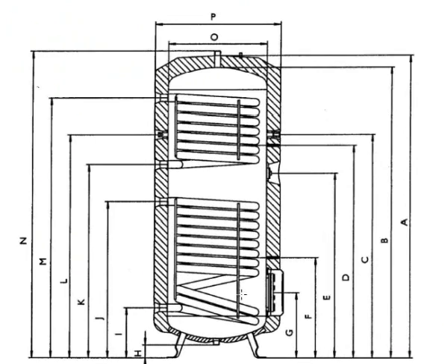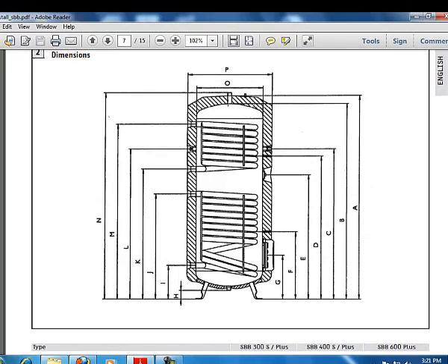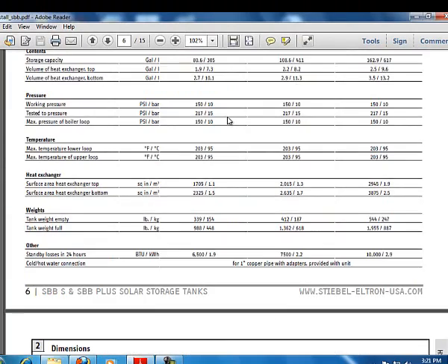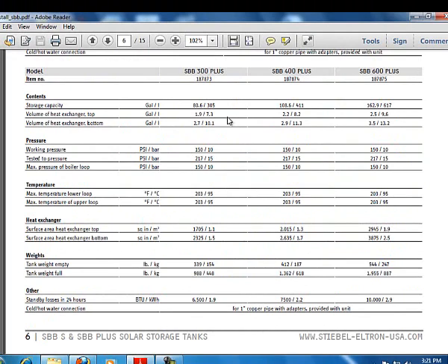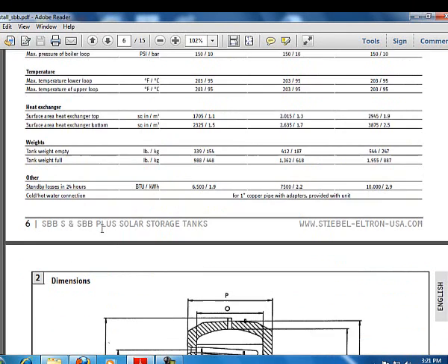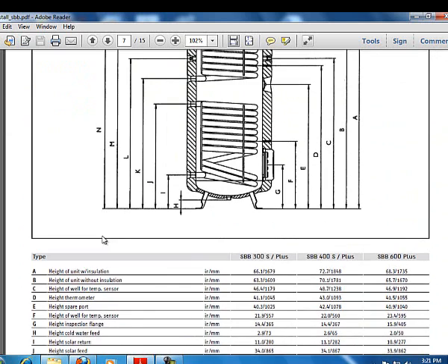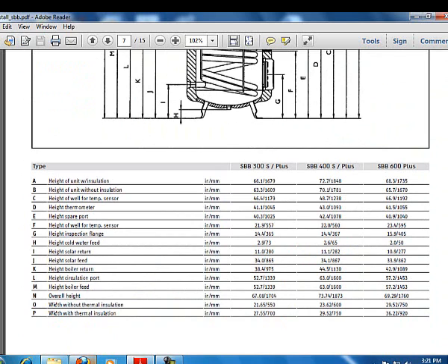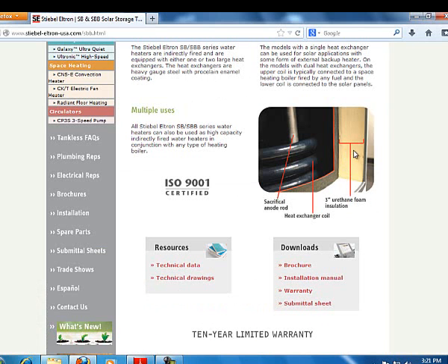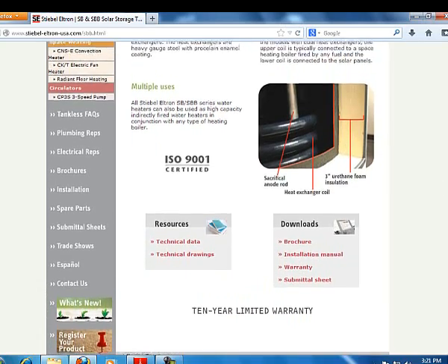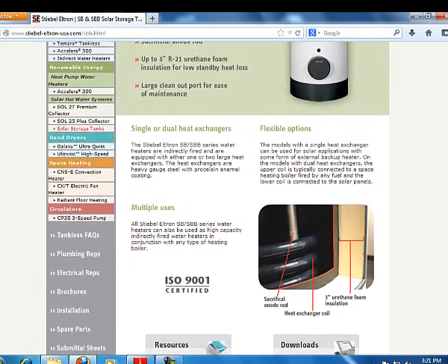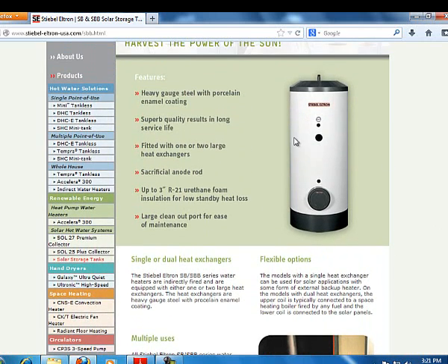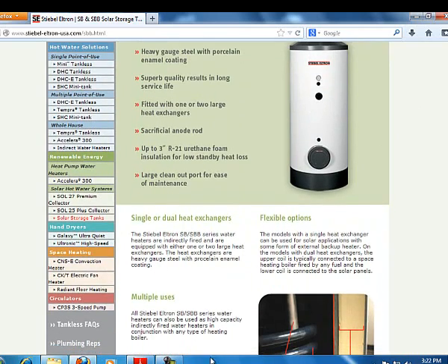You can kind of see how this tank takes the hot water and exchanges it here. It takes this to the boiler or potentially the domestic hot water if it needs to be double-lined. If you're allowed to use the single-line version, you can take that water right off to there. There's a couple things that you need to know about. One thing that you need to know is what is the amount of surface area that we have for heat exchanging. Not as critical, but we also need to know what the height and the dimensions are of this product, and the reason for it is where are you going to store this tank at. The nice thing about this tank is that it's insulated. It's got a three-inch insulation around it. Unlike that open vent where you're going to have to then provide your own type of insulation around it, this has got it built in, so most typical installs will have this sitting next to the domestic hot water tank, and that will give us a means of giving us a nice, clean look going to and from the tank to this storage tank. And that's what we have here with this 300-gallon system, and that will do it for us.